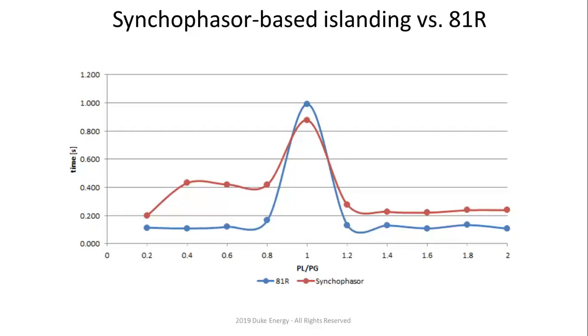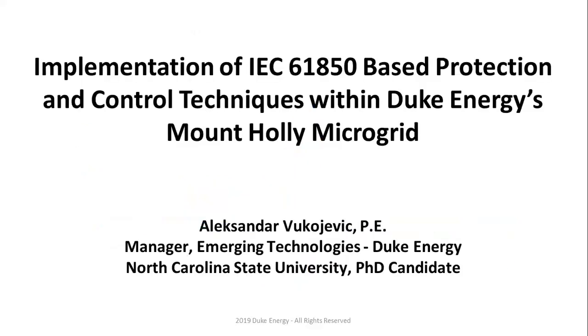So after about 6,000, 7,000 operations, it's not the same response time as after about 1,000 or 2,000, right? Some of these times were not done at the same time as some of the stuff you have seen. So you can clearly see the synchrophasor-based islanding works. As expected, it's slower than 81R. Also, it's slower than 81U or 81O. But for PL over PG equals 1, that's the sure way to detect it the fastest way, right?